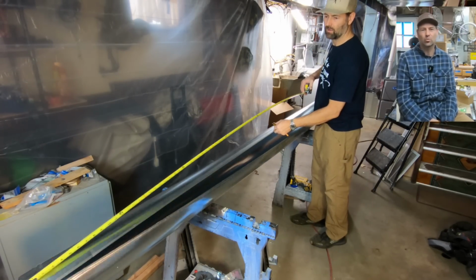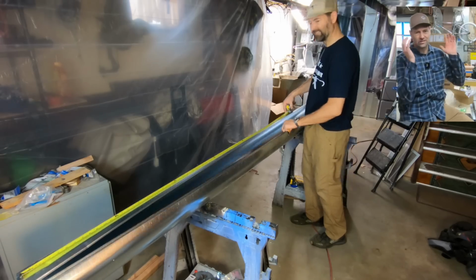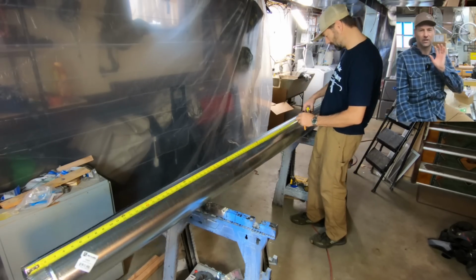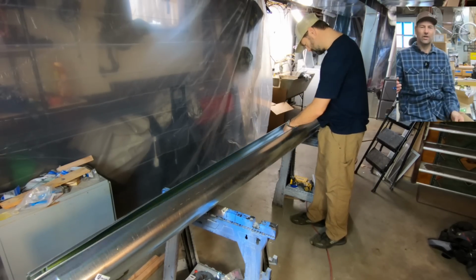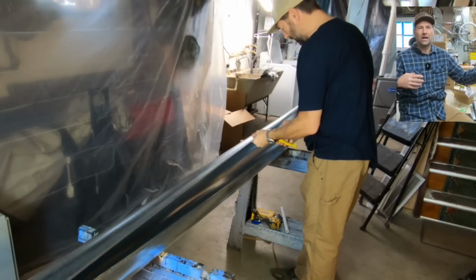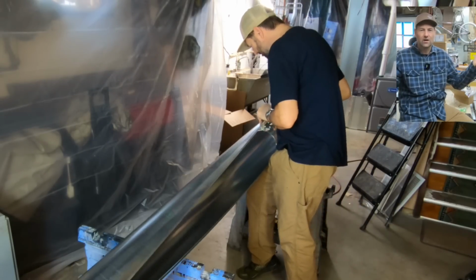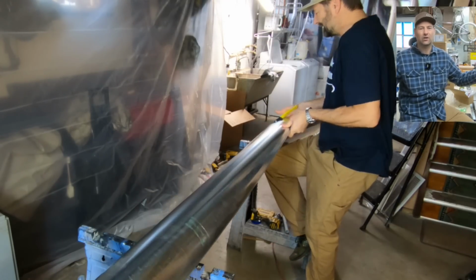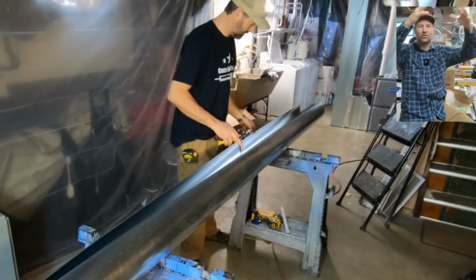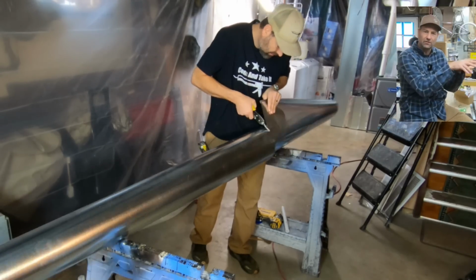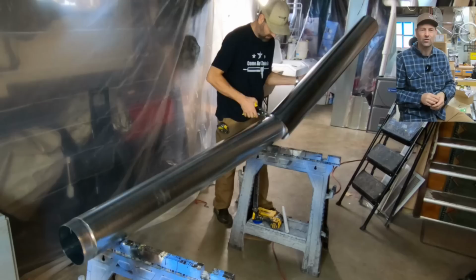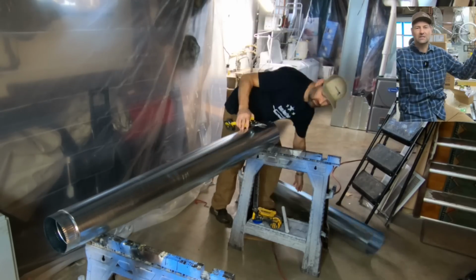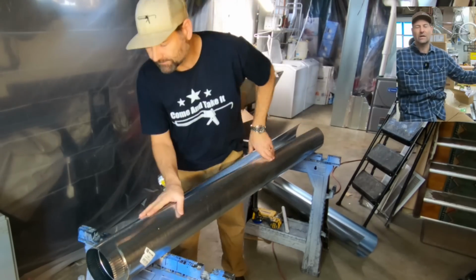Now there are general rules of thumb. You have to step down your trunk lines to keep the velocity of the air up so that at your furthest away registers, there's enough air and speed to throw the heat out into the room to mix in. If you just have a little bit of heat puttering out of your heat register, it's not going to mix into the room or heat the house.